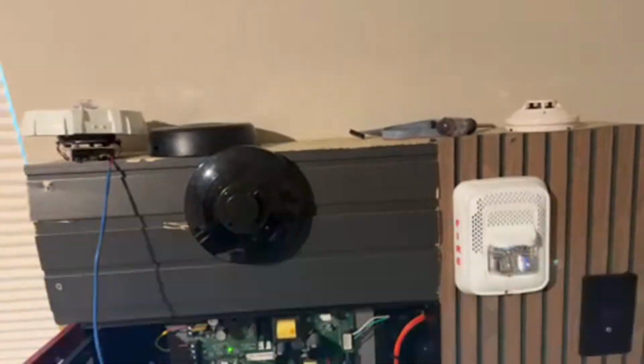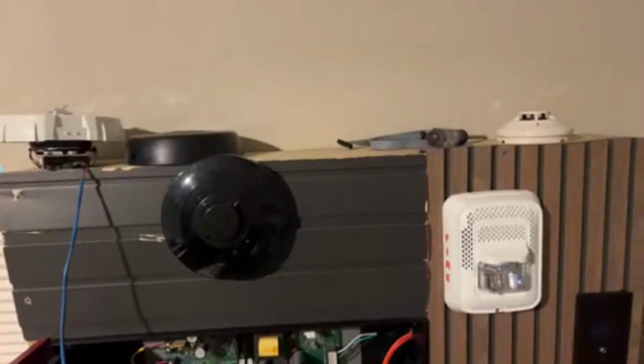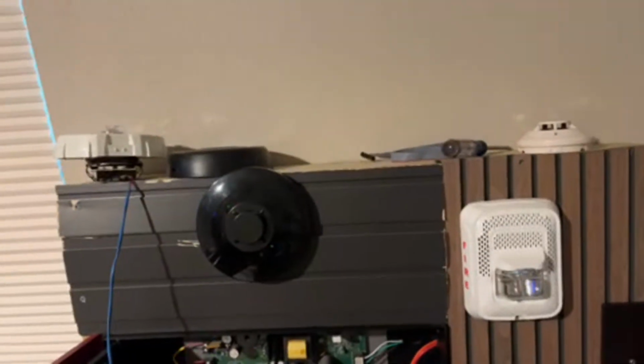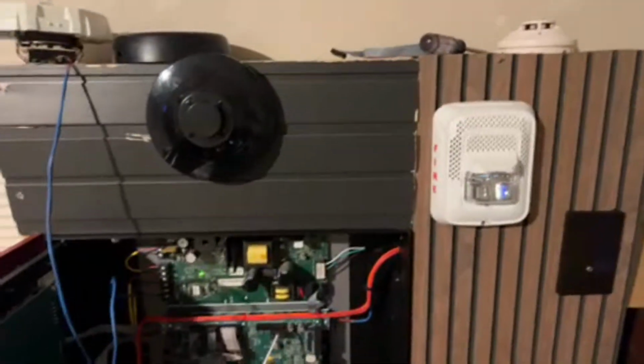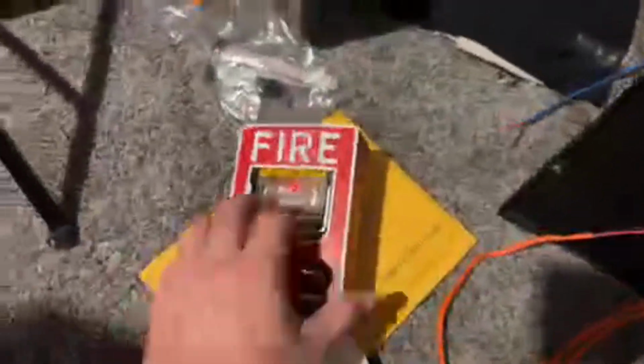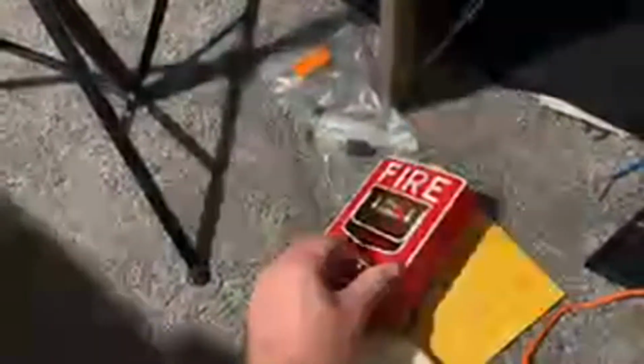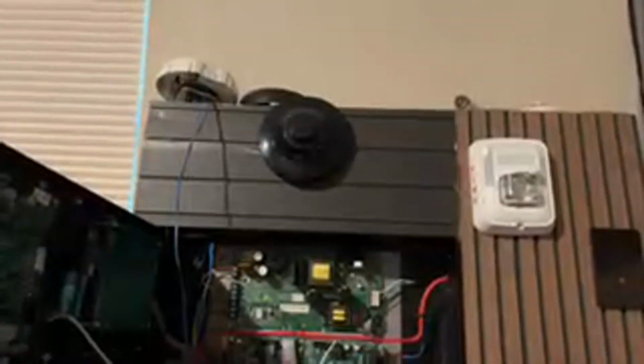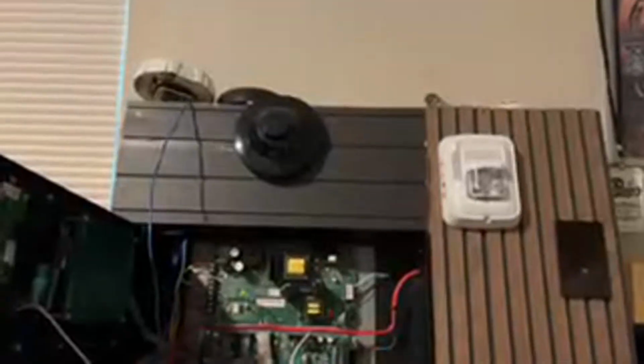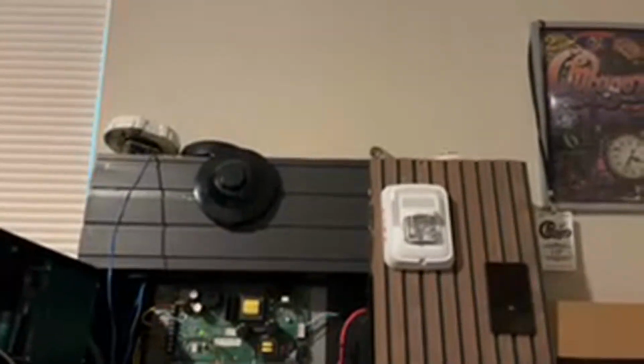I am proud to report that these strobes will stay in perfect sync. Wow. All this time I thought with Gamewell you could only do one sync protocol, but that's per node, apparently. You can only do one sync protocol across an entire system, which would basically be an entire node. But if you have multiple nodes, you can do different sync across those nodes. And they will stay in sync. Dude, that is awesome.